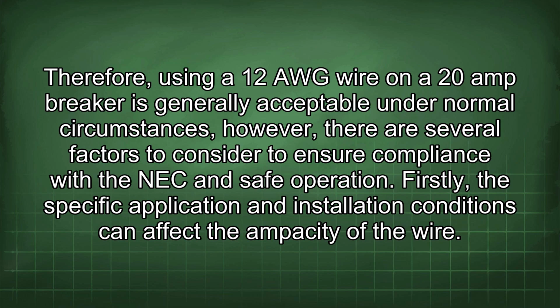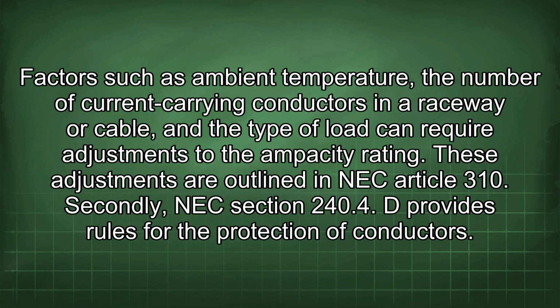Firstly, the specific application and installation conditions can affect the ampacity of the wire. Factors such as ambient temperature, the number of current-carrying conductors in a raceway or cable, and the type of load can require adjustments to the ampacity rating. These adjustments are outlined in NEC Article 310.